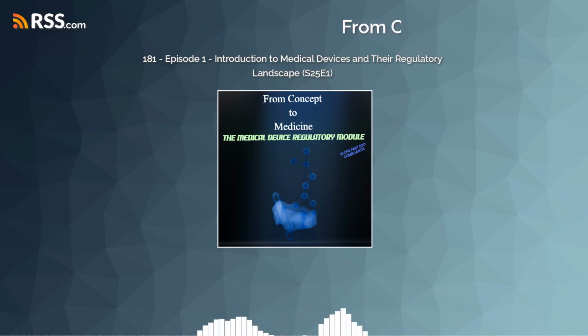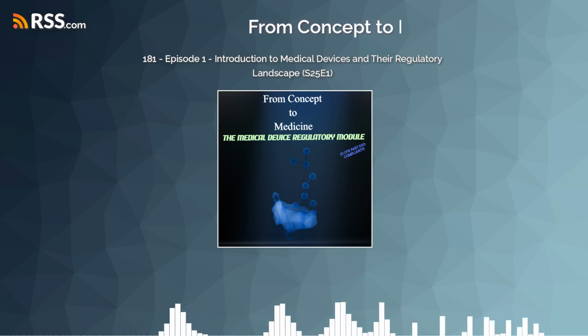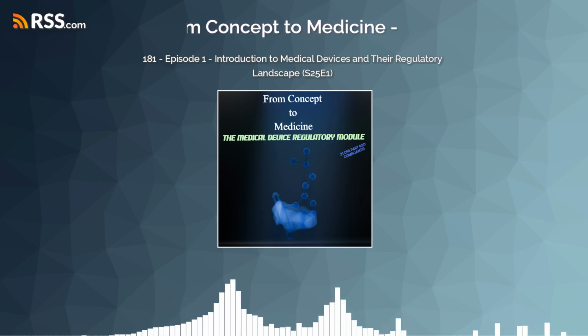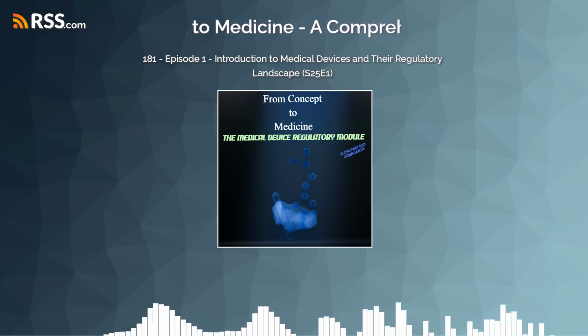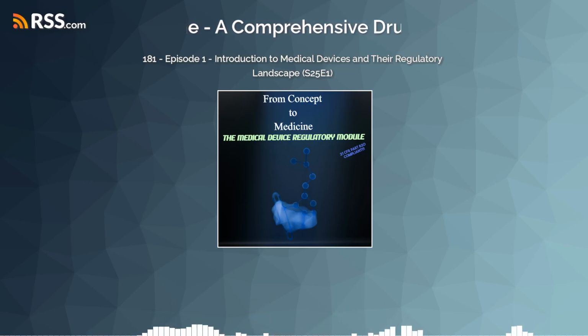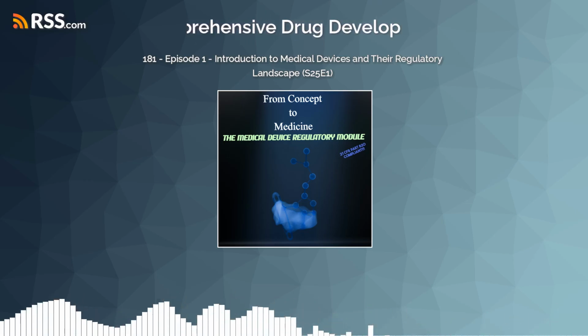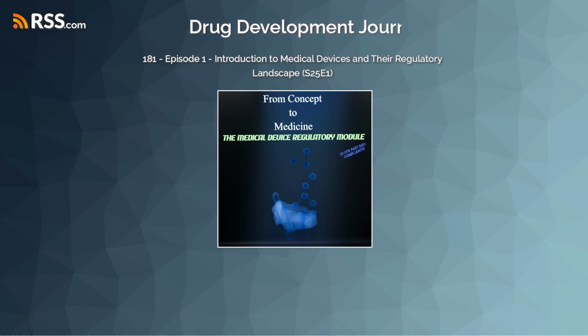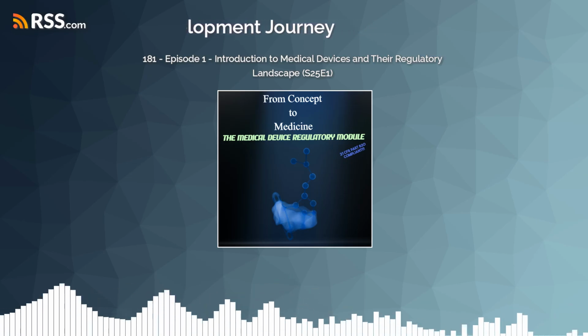Exactly. And all of this history, the whole chronological story of the design process, is meticulously documented in a design history file, or DHF. The DHF, the design story. It's the full narrative, yes. So the DHF is the design story.